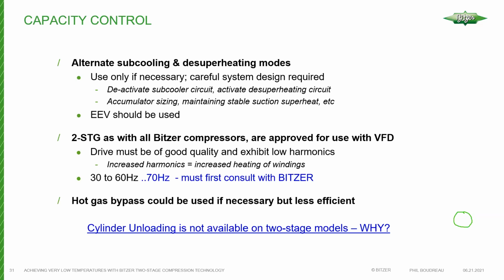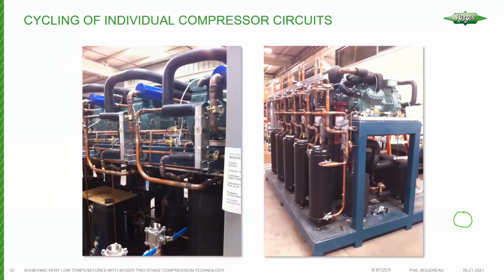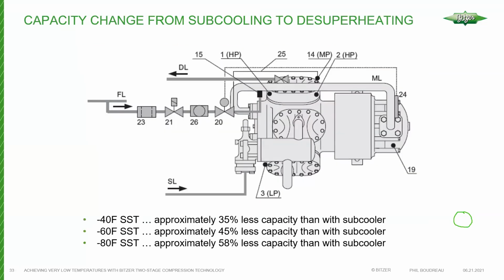Just when you're using drives, I know I've mentioned this before with VFDs, for anyone who's attended some of the other webinars where this has come up, generally you want to use a drive that has a good quality and exhibits low harmonics. Harmonics in the supply to a compressor's terminals always result in heat. So we can have multiple compressors and stage them, but we cannot apply any unloading, of course, because unloading is simply not available, as we need all of the cylinders to accomplish both stages of compression.